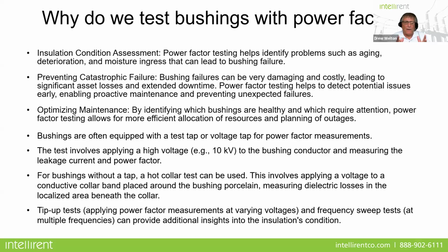So for bushings without a tap, again, as I said, you could always use what's called a hot collar, or a thing that looks like a rubber band that goes around the porcelain on the outside of the bushing to actually do the measurement. Another thing we like to do is what's called a tip-up test, and that is measuring the power factor at various voltage levels and making sure you're getting the same results.